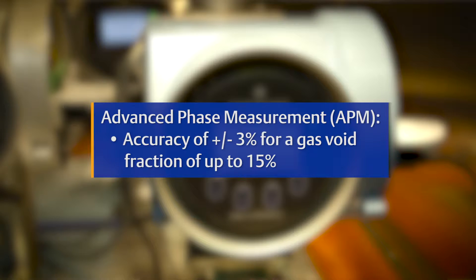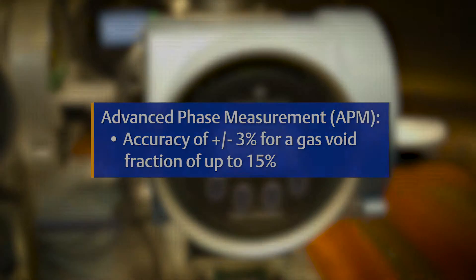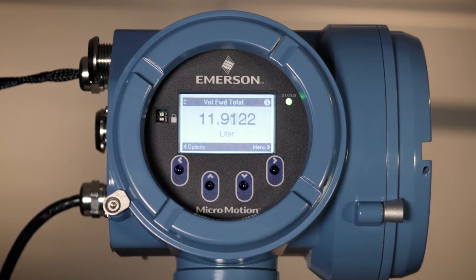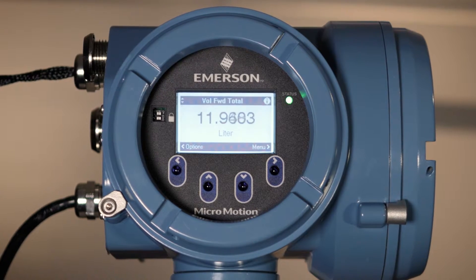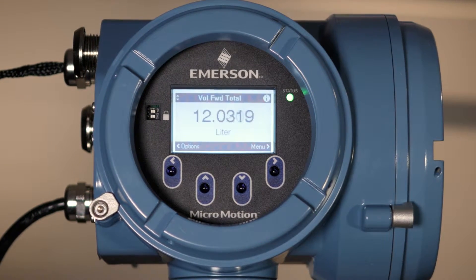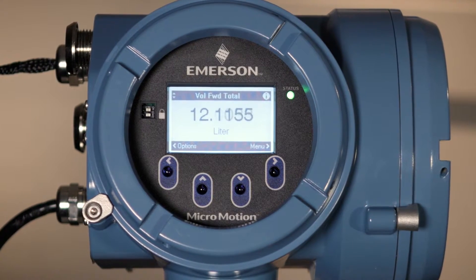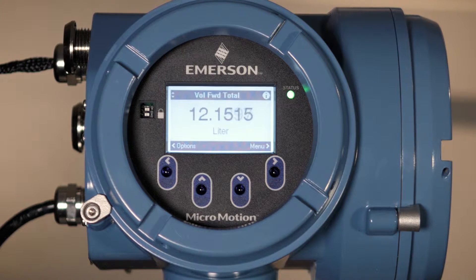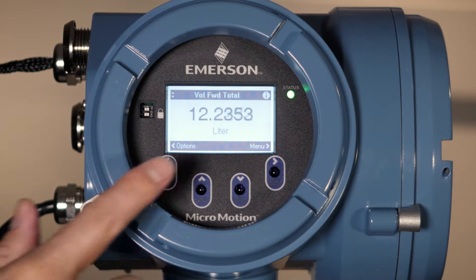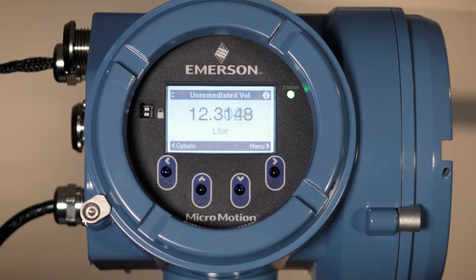APM is capable of providing an accuracy of plus or minus three percent for a gas void fraction up to 15 percent. When multi-phase flow is present, the software corrects the mass and volumetric flow parameters and provides corrected values as an output. These values are also referred to as remediated flow values.